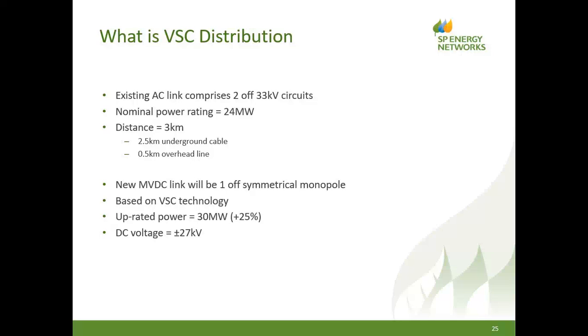This scheme will now operate at 30 megawatts, a 25% uplift of power compared to the existing AC system. We've been quite prudent in our design of the system. We're trying not to push the technology too hard because of the existing AC circuits and perhaps the age of the cables. So we've chosen a DC voltage of plus or minus 27 kV, a fairly esoteric number, but if you do the sums, 27 kV represents the peak of a 33 kV phase to ground voltage. So 33 over root 3 times root 2 equals 27 kV.